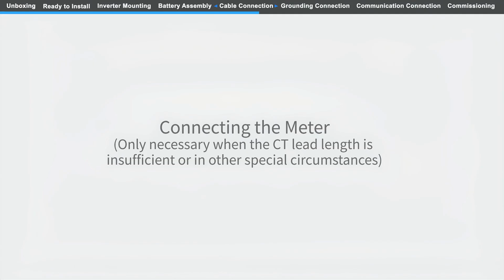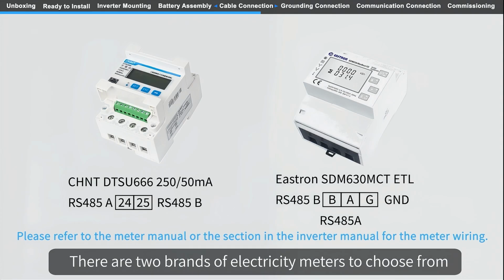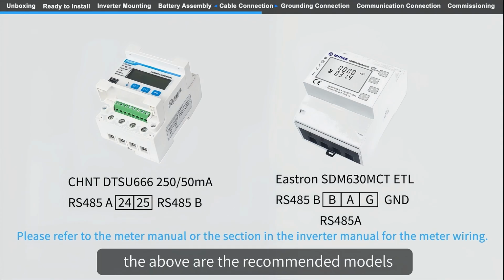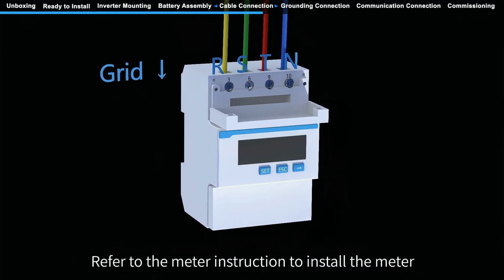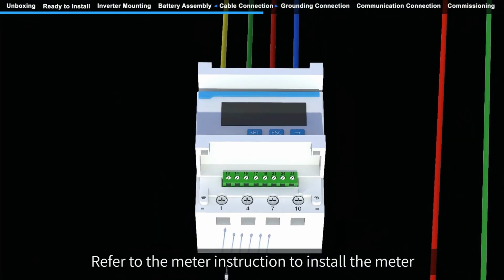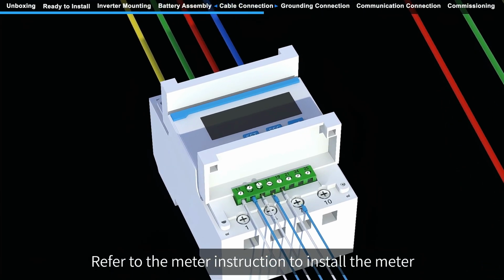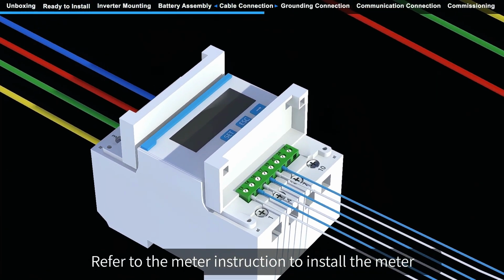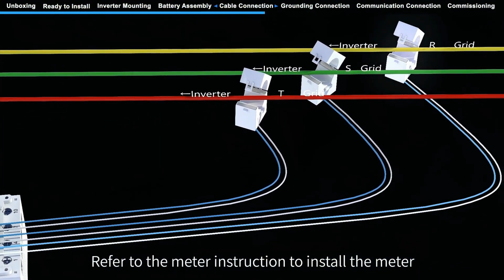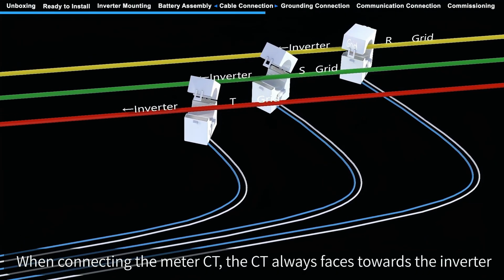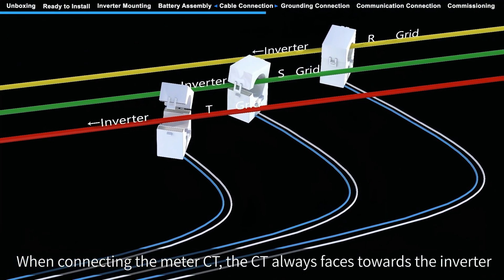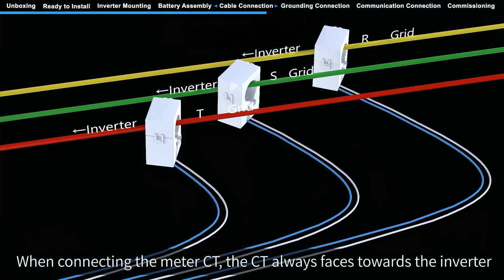Connecting the electricity meter. There are two brands of electricity meters to choose from. The above are the recommended models. Refer to the meter instruction to install the meter. When connecting the meter CT, the CT always faces towards the inverter.